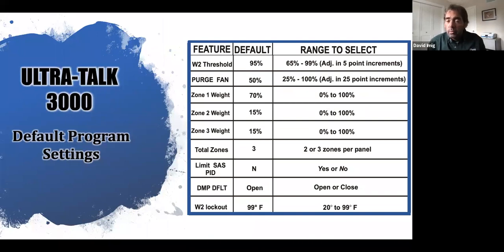The W2 threshold is a percent, and this is a formula that we're looking at. This is a percent of system demand that we get in heat pump operation where we bring on auxiliary. This will make more sense, and we'll review this in a bit, but when I get to 95%, if I have not achieved my target temp, I will bring on auxiliary. You'll see that you have a range of 65% to 99%, so that may be something you adjust in the field.